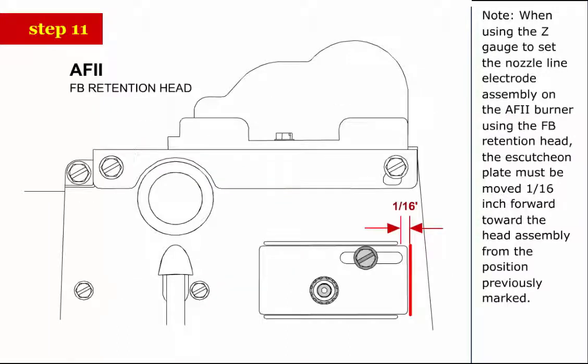Note: When using the Z gauge to set the nozzle line electrode assembly on the AF2 burner using the FB retention head, the escutcheon plate must be moved 1/16 inch forward toward the head assembly from the position previously marked.